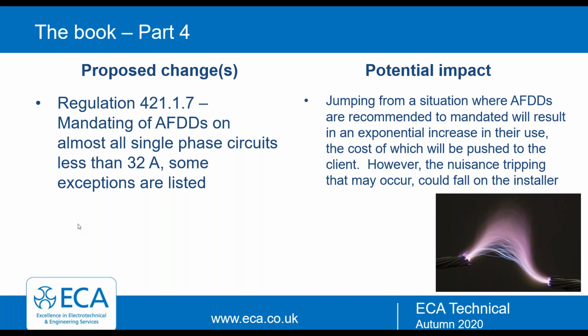With reference to AFDDs, I have questioned a manufacturer on their use on lighting circuits, and they believe they provide protection, although I've heard what you referenced with regard to a minimum arc fault current. What does BS 62606 say, the British standard for AFDDs? My information has always come from manufacturers on that, and they do talk about having a minimum load. So it'll be right to say that they could work on lighting circuits, but they just would need that minimum load. I'm guessing most of us now have got LED lights on our lighting circuits, which don't provide that load.